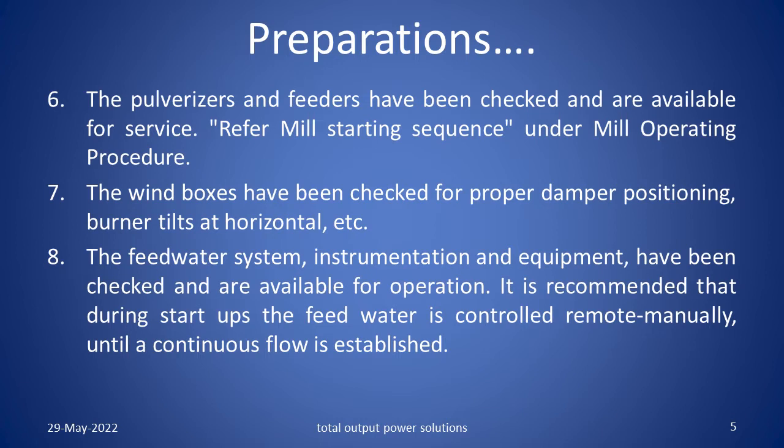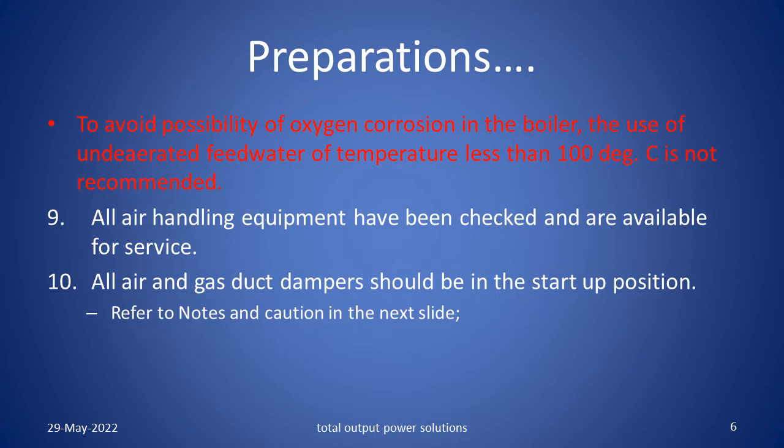The feed water system, instrumentation and equipment have been checked and are available for operation. It is recommended that during start ups, the feed water is controlled remote manually until a continuous flow is established. To avoid the possibility of oxygen corrosion in the boiler, the use of undeaerated feedwater of temperature less than 100 degrees centigrade is not recommended. All air handling equipment have been checked and are available for service. All air and gas duct dampers should be in the start up position.